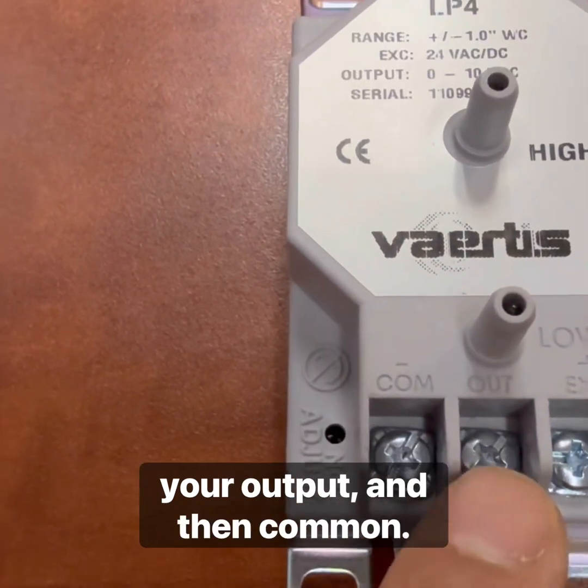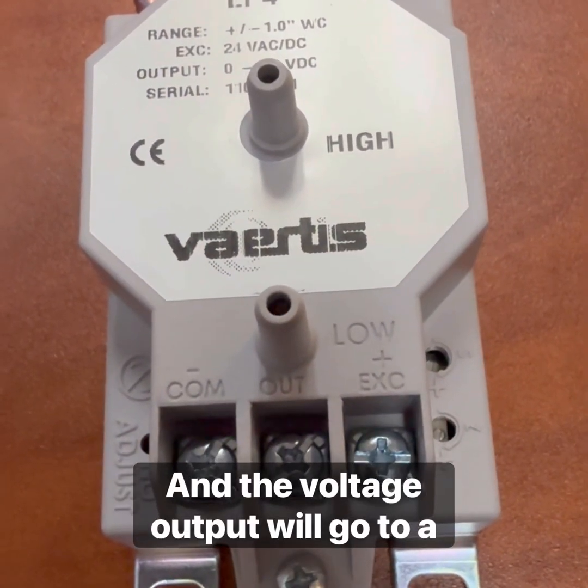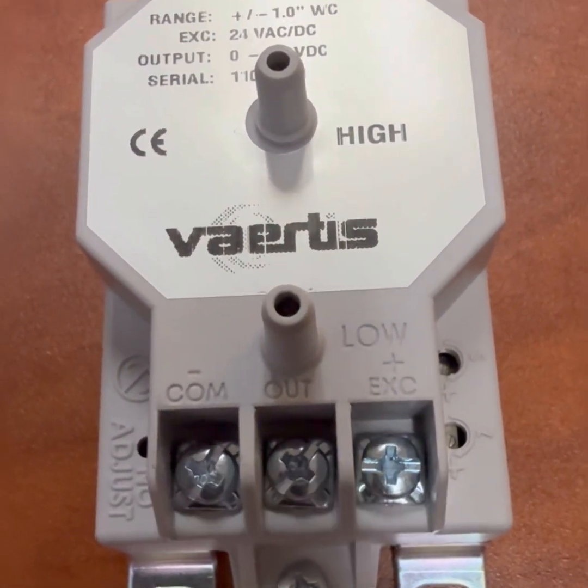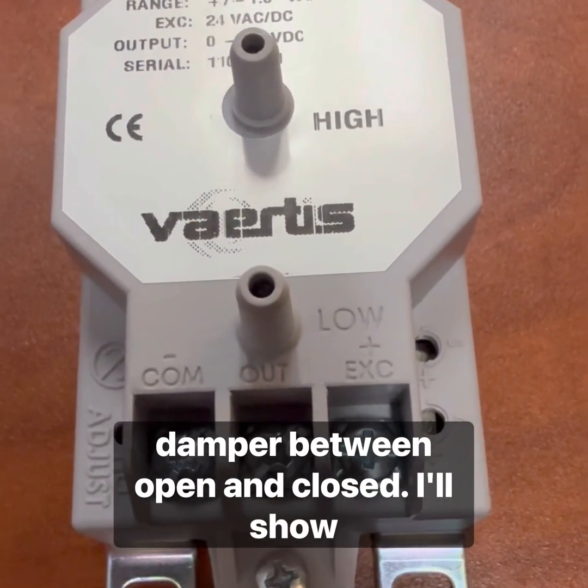3 wires needed. You need power, 24 volts, your output, and then common. And the voltage output will go to a controller, and the controller will use that signal to ramp up or ramp down a fan depending on the pressure, or it can also be used to modulate a damper between open and closed. I'll show you how this is wired and what this looks like installed.